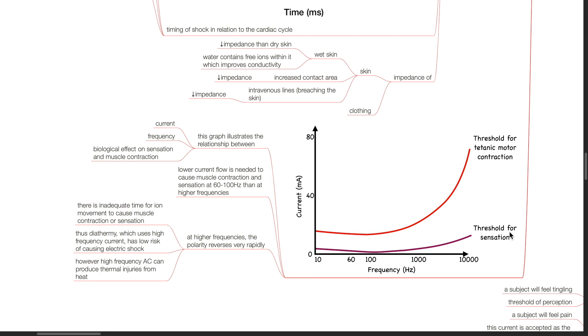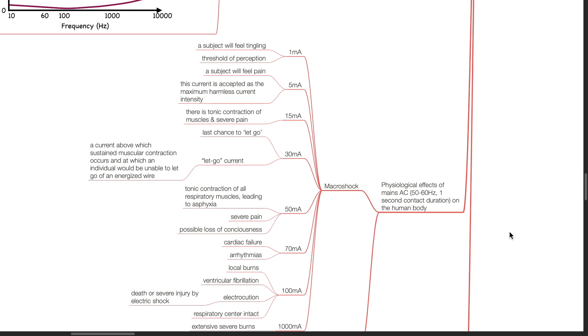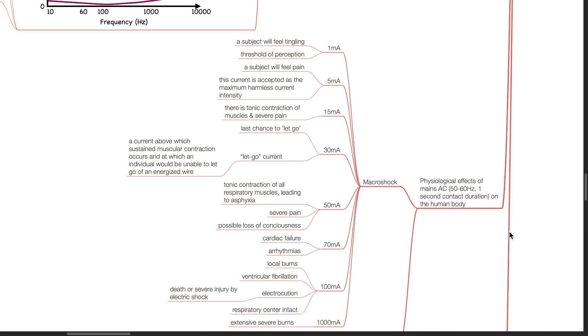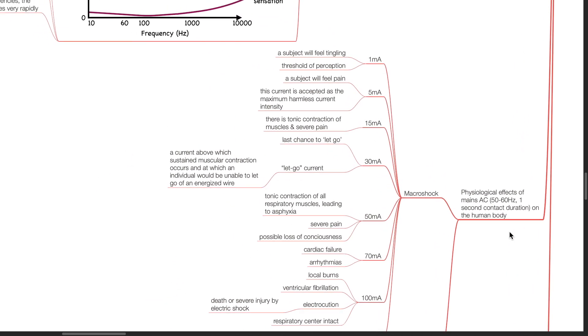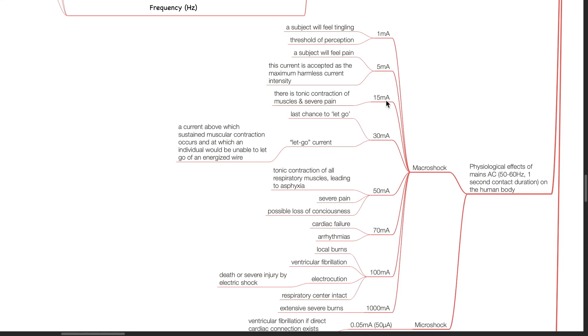Physical effects of mains AC 50 to 60 Hz at 1 second contact duration on the human body. This can result in macroshock and microshock. For macroshock, at 1 mA the subject will feel tingling. This is the threshold for perception. At 5 mA a subject will feel pain. This is the current accepted as the maximum harmless current intensity. At 15 mA, there is tonic contraction of muscles and severe pain.